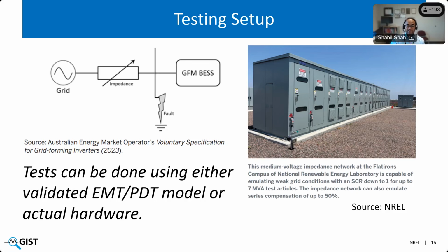Moving on to the testing setup. The test setup is quite simple. Basically, we connect the grid forming resource to an ideal voltage source with a reactor, a variable impedance, in between, and that is how we test the grid forming resource. The variable impedance here is to achieve a particular grid strength for the test, and we'll talk in a minute about why we might need to use different grid strengths for testing a grid forming resource.